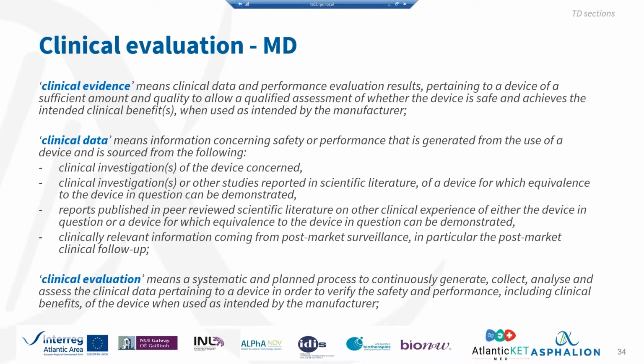So now let's talk about the clinical evaluation. There are three concepts we have to keep in mind: clinical evidence, clinical data, and clinical evaluation. What is each thing? Clinical evidence is clinical data and performance evaluation results that pertain to a device of a sufficient amount and quality to allow a qualified assessment of whether the device is safe and achieves the intended clinical benefit when used as intended by the manufacturer.